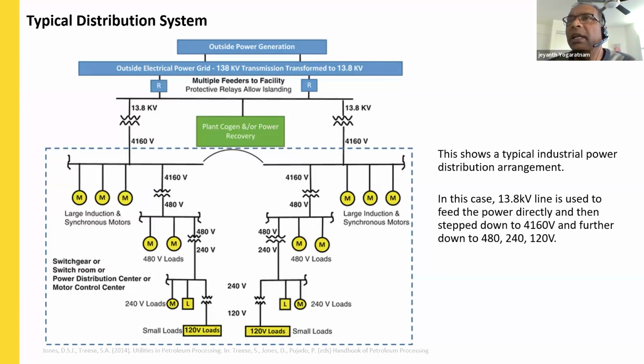Let's look at the types of loads connected at each and every bus. When you look at the 4.16 kV level, you see the large induction and synchronous motors. We know that in industrial applications, medium voltage motors are very common because they are used for high horsepower applications. Those motors are connected in this particular case at the 4.16 kV level. And further, a transformer steps down to 480 volts, and the 480 volt bus is connected to 480 volt loads, which could also be low voltage motors. And further, the 480 volts steps down to 240 volts or maybe below 120 volts to provide supply to the lighting loads, receptacle loads, and any other auxiliary loads you find in the plant.